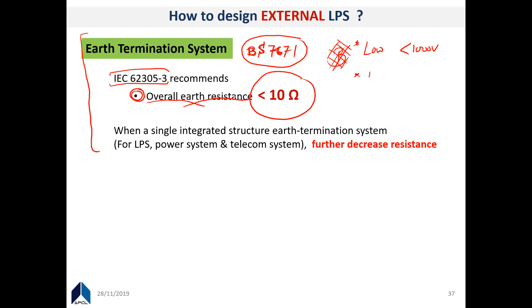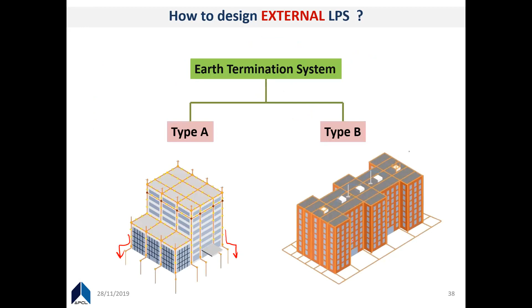So the earth termination system shall be less than 10 ohms, and there are 2 types of earth terminations you can come up with: either individual electrodes to individual down conductors, like here, or an interconnected system like this, a ring system interconnected.